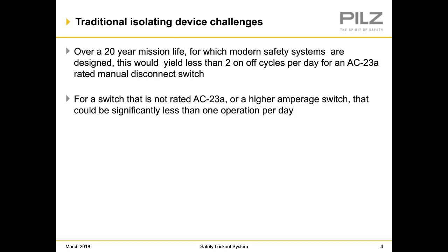Over a 20-year mission life for which modern safety systems are designed, this would yield less than two on-off cycles per day for an AC23A rated manual disconnect switch. For a switch that is not rated AC23A, or higher amperage switches, that could be significantly less than one operation per day. And I'm sure everybody might have applications where their use of a lockout switch is significantly more frequent than that.